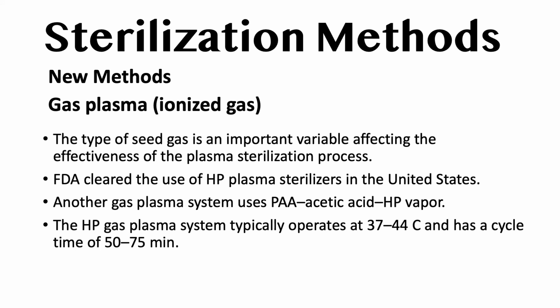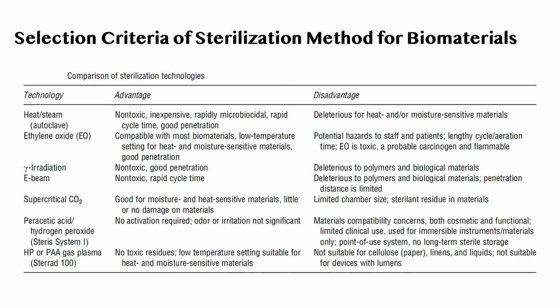The type of seed gas is an important variable affecting the effectiveness of the plasma sterilization process. The FDA cleared the use of the hydrogen peroxide plasma sterilizer in the United States. Another gas plasma system uses acetic acid and hydrogen peroxide vapor. The hydrogen peroxide gas plasma system operates at 37 to 44 degrees centigrade and has a cycle time of 50 to 75 minutes. Selection criteria of the sterilization method for biomaterials are summarized in this table.